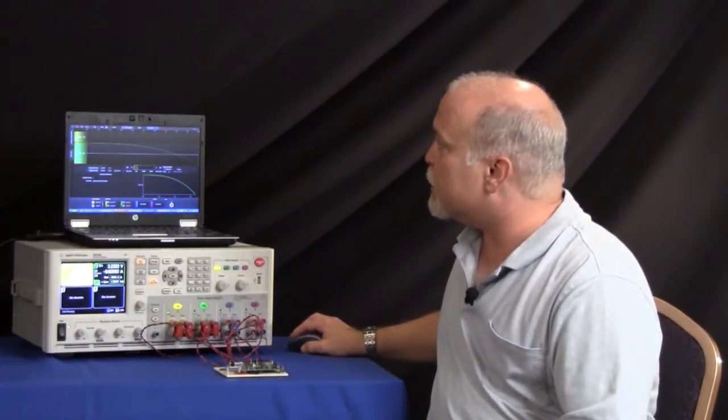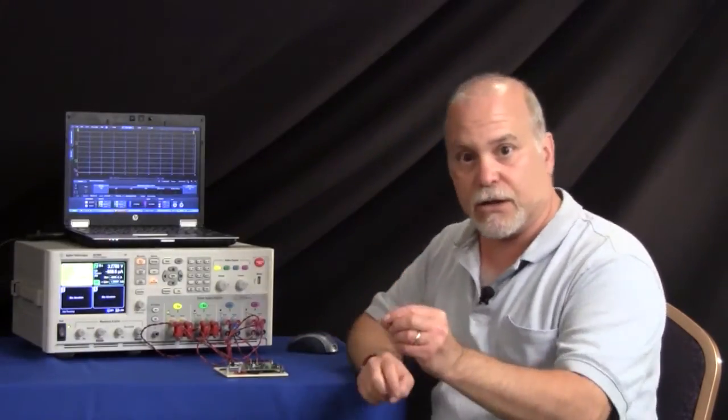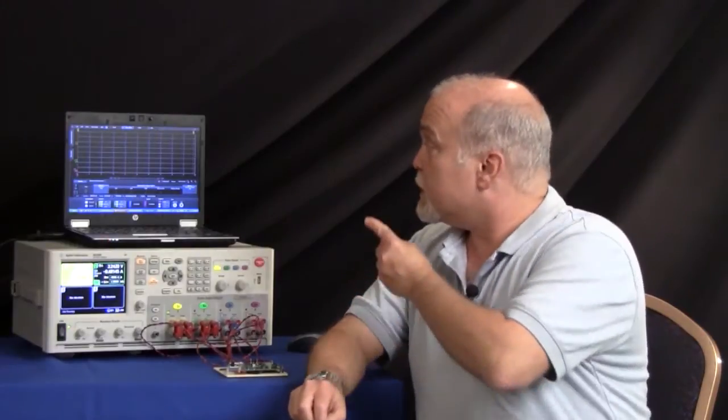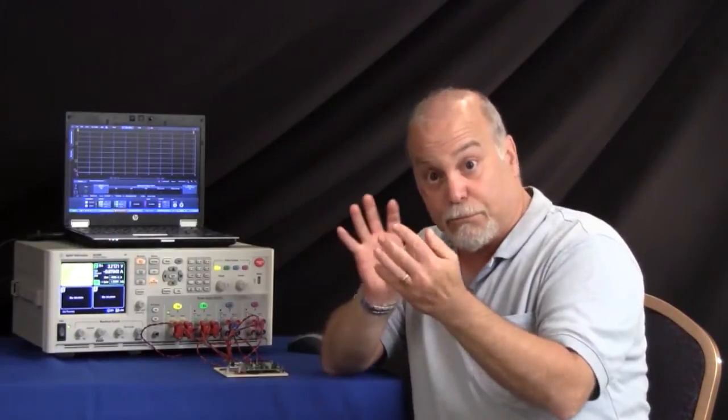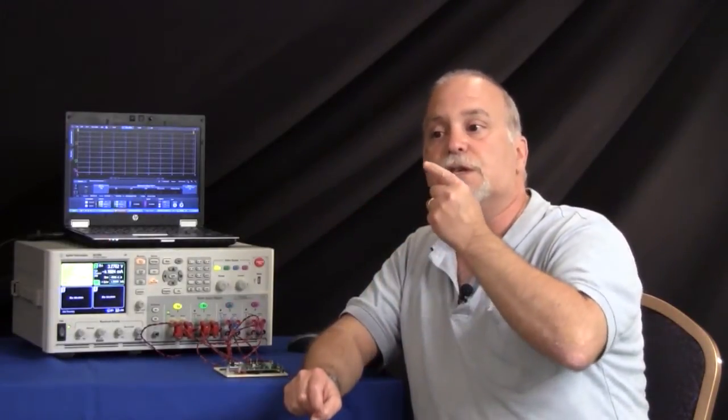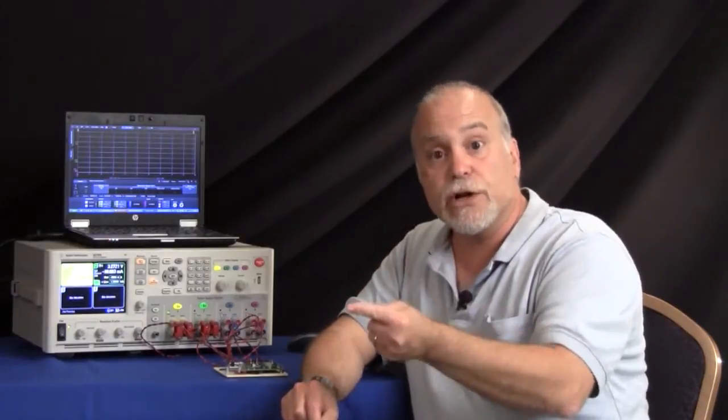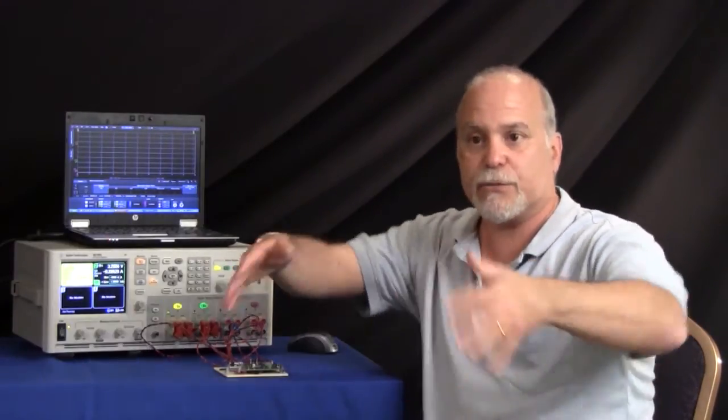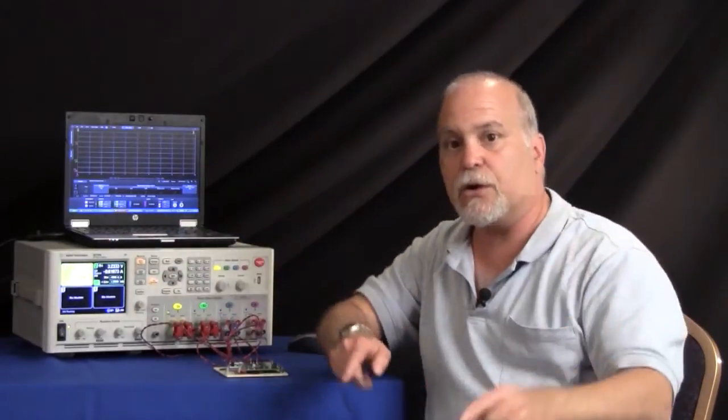So what we're going to do now is we're going to start the data logger, and then we're going to start the arbitrary waveform generator. And because this is an integrated instrument, one of the key features is since they're both in one box, we can cause the data logger to be triggered when you start the arbitrary waveform generator. And normally you'd have separate instruments, and you'd have to be pushing buttons on all of them because they're integrated. They can work together.